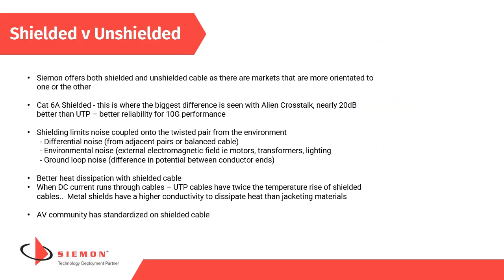Here are a few of the main reasons as to why we recommend shielded cable versus unshielded. Wi-Fi, AV, DAS, which stands for Distributed Antenna Systems, PoE, which stands for Power over Ethernet, are all technologies that perform best with shielded cable. Shielded cables offer better protection from noise generated by devices such as motors, transformers, lighting, all things that you'll find in a ceiling environment where cables run.